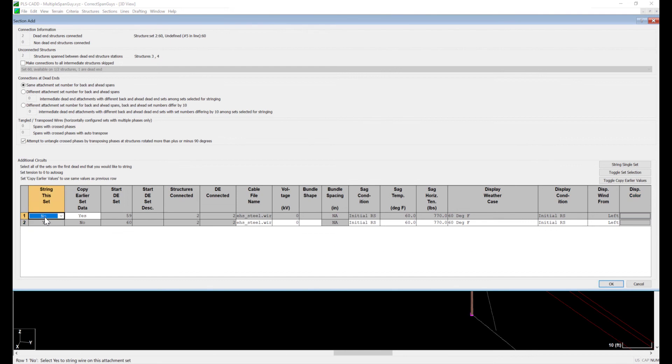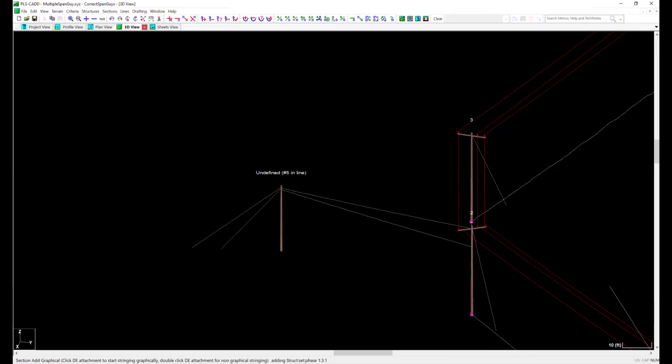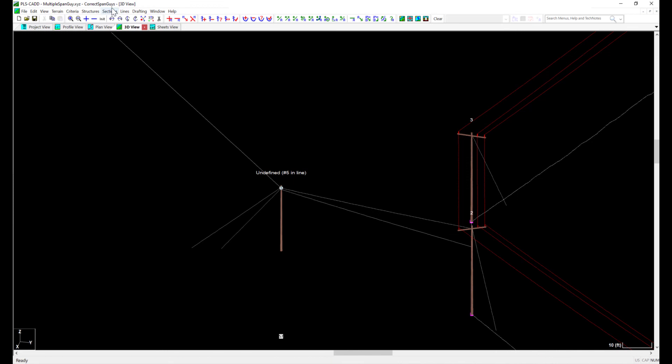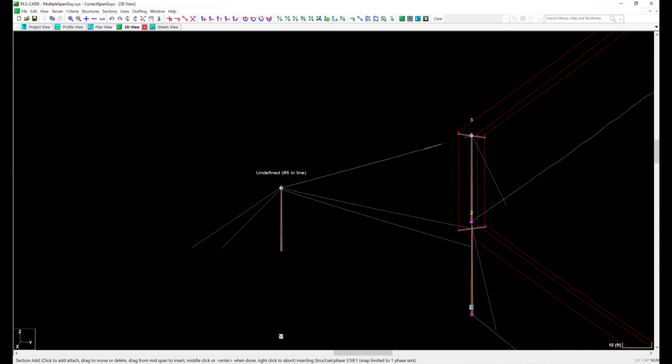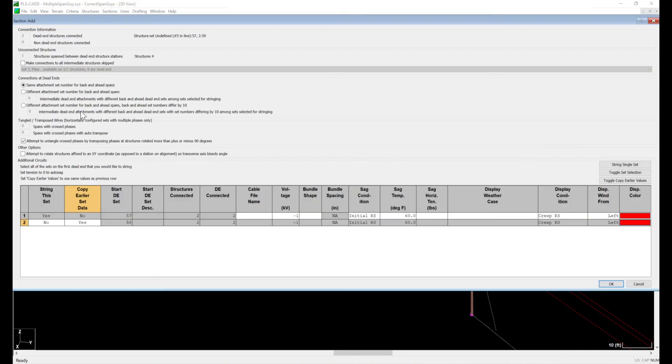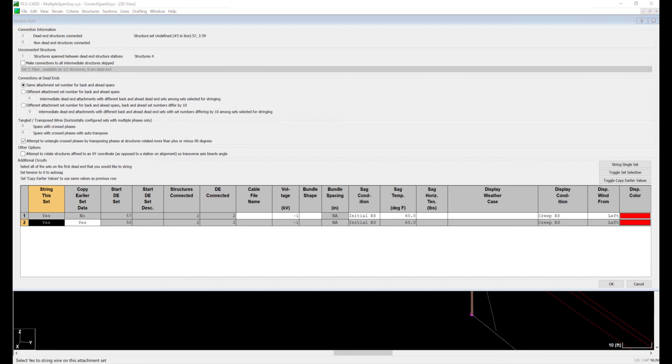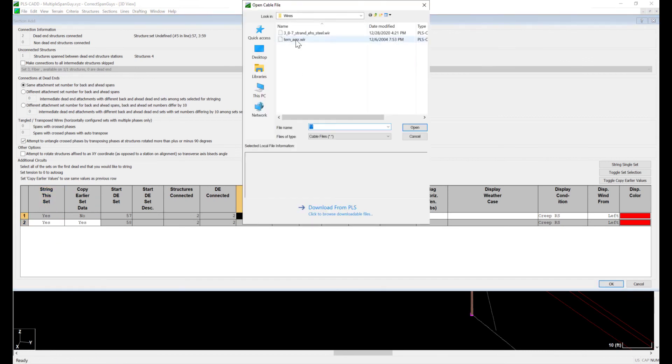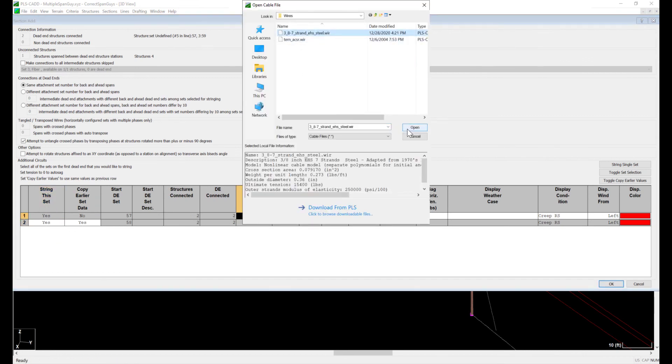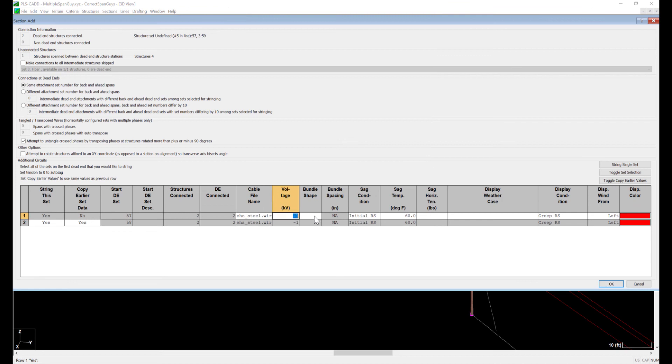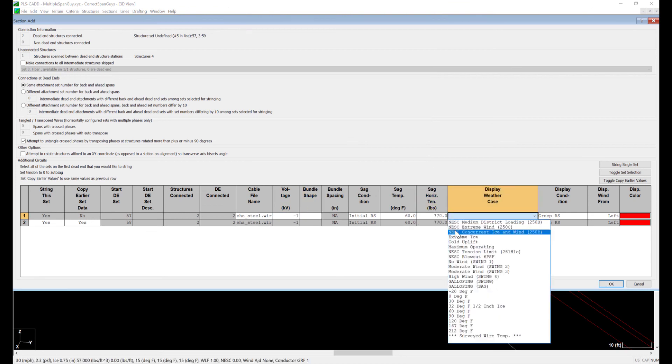I'm using 5% as an estimation. The PLS CAD manual recommends a value of 2% to 5% of rated breaking strength, or at least a value greater than the self-weight of the wire. This is an approximation as most construction crews will not install guys with a specific sag or tension value. The suggested values are typically enough to pull the slack out of wire.